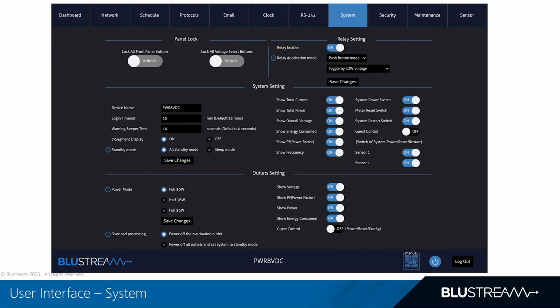Establish defaults for names, startup states, and sequencing, and configure overload processing—basically what the unit should do if a channel exceeds limits. Options might include warning only, timed retry, or an automatic shutoff to protect connected gear. In short, the system tabs give you the keys to lock down the front panel, standardize relays, declutter the UI, and enforce safe outlet behavior, so your installs are consistent, secure, and protected.